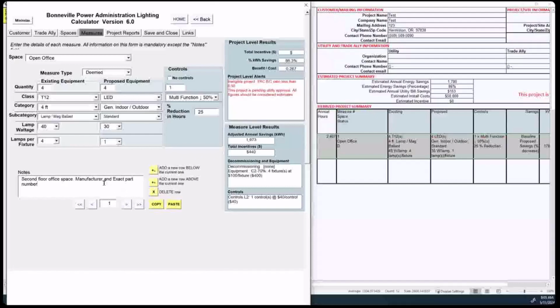A best practice that I always recommend is if you have a multi-wattage fixture, start out with the lowest wattage setting when you install that fixture. Because if you start out with the lowest setting and the customer says, I was really kind of hoping it'd be a little bit brighter in here, or they're absolutely irate and say, this is not bright enough for what we do in here, you have somewhere to go.